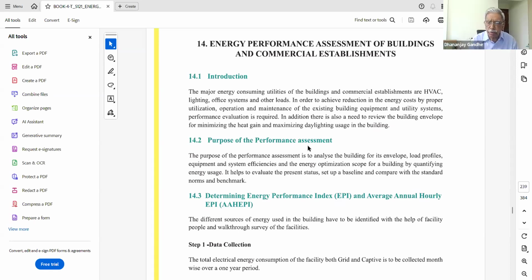What are the system efficiencies for the HVAC system, and also we have to find out the total cooling loads. We have to find out the total lighting loads. Also calculate certain ratios which we compare with the standard ratios to find out whether we are operating within limits, whether the electrical load is within limits, what the air conditioning loads are, and what the performance of the system is.